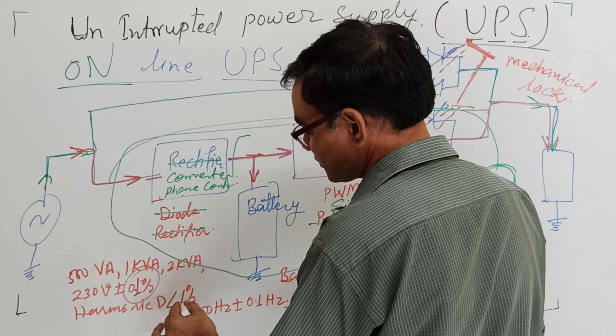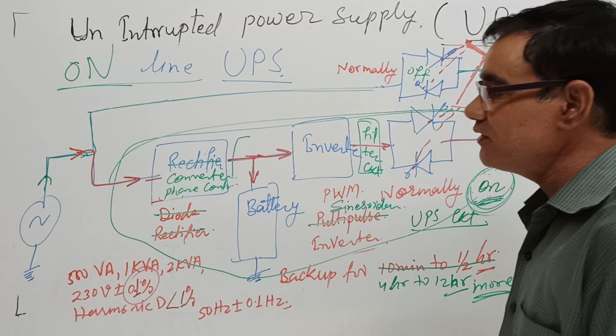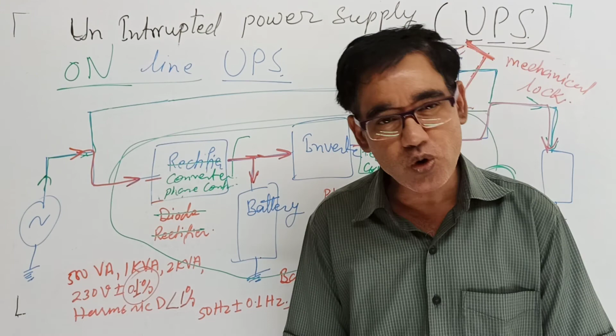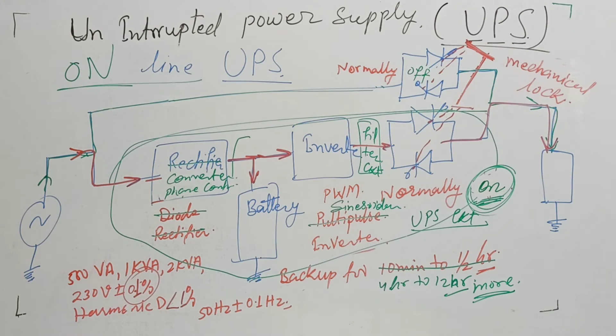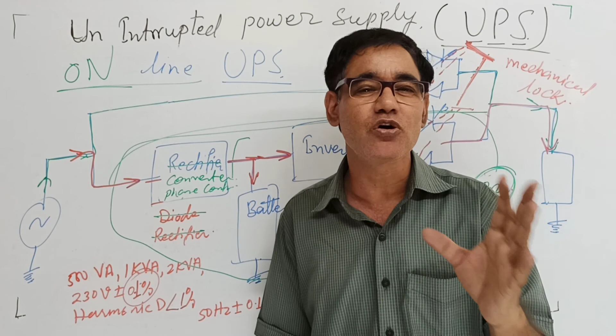There is protection: over voltage, under voltage, over frequency, under frequency, over current, and overheat protection. So all kinds of protections are provided in this online UPS as compared to the offline UPS. The response time is less than 5 millisecond, so it gives very good dynamic response. There is no fluctuation in the output. In this way, the online UPS is far better than the offline UPS.